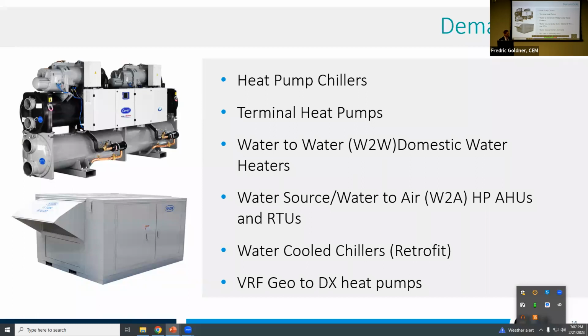So all the benefits of inverter compressors and modulating compressors and match loading, hot gas bypass reheat, all of that can now be done on a geothermal loop, which will really open doors to the existing building retrofit. And I say that because the VRFs of the world are already being used to retrofit buildings, and we're just plaguing rooftops and the grounds with the outdoor units.